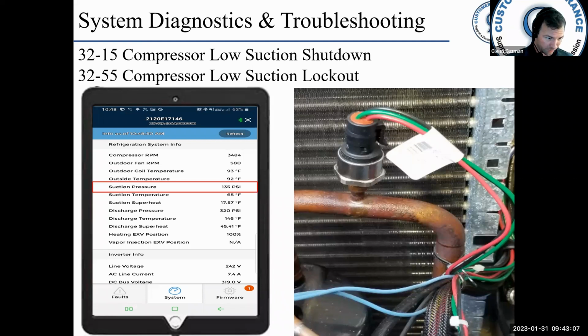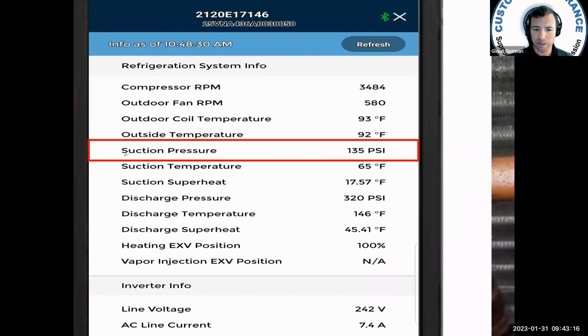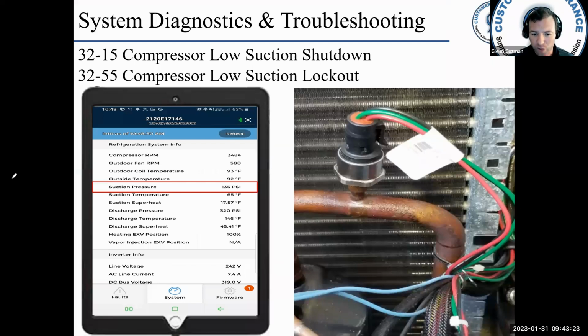So if I had this fault, what I would do is look at my suction pressure on the app or on the UI. Okay, you can see here suction pressure 135. All right, when I connect my gauge, is it reading reasonably close to 135? If I read 137 on my gauge, okay, I'm happy with that. Now if I read 200 on my gauge, well, that's a problem. But as long as it's reasonably close within a couple psi, then you should be fine.